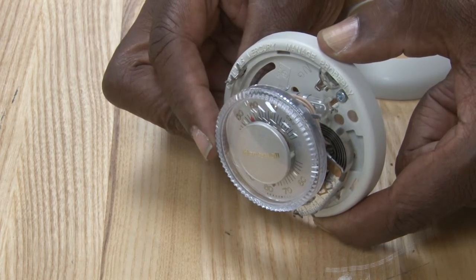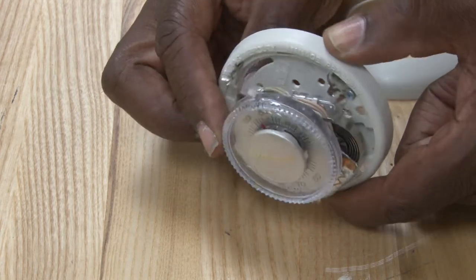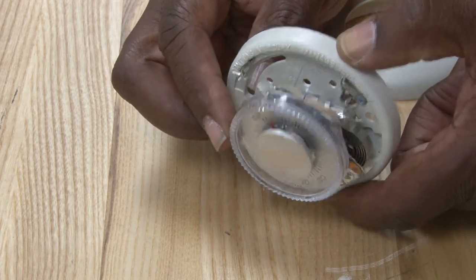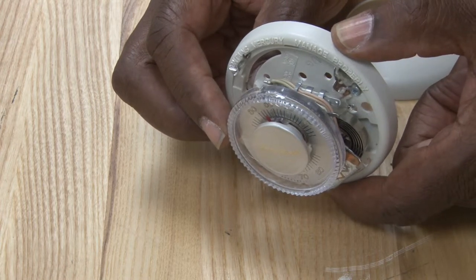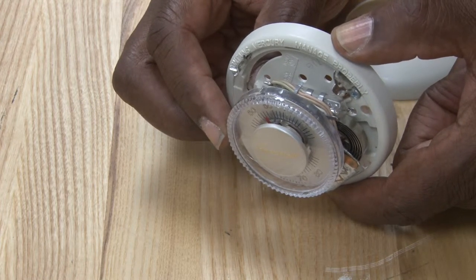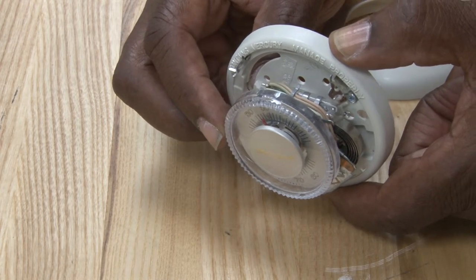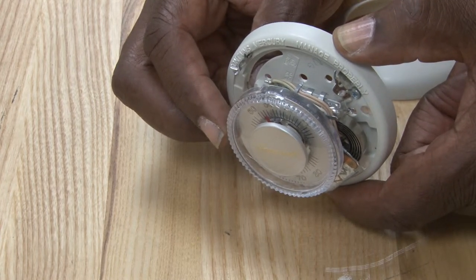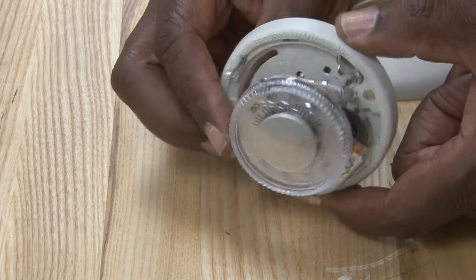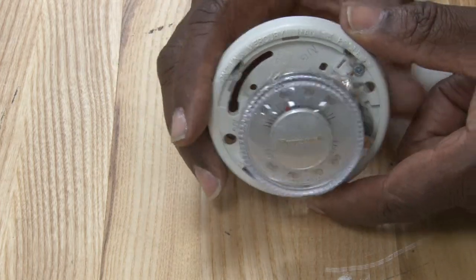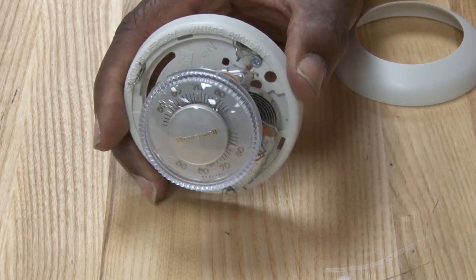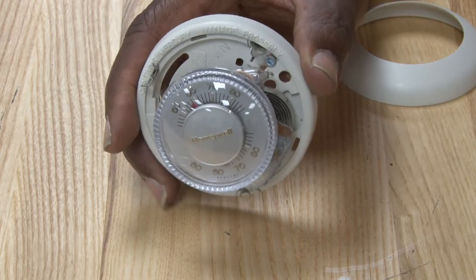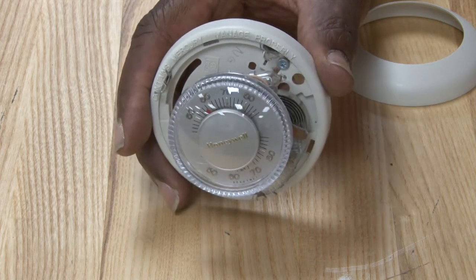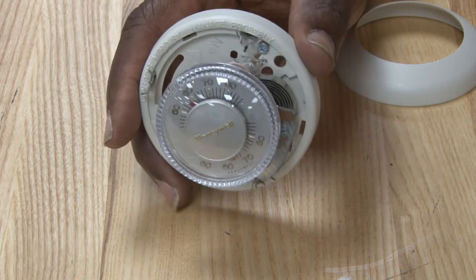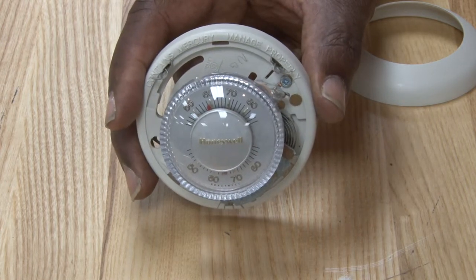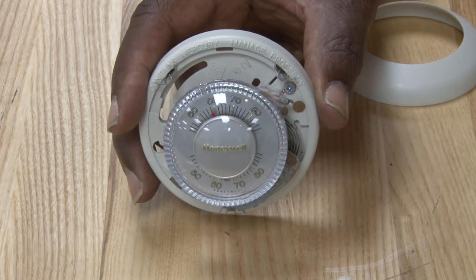This is one type. This old style, they're getting rid of these because, of course, mercury is a hazard. It's toxic. So because of that, digital thermostats are becoming more popular these days. Matter of fact, digital is a lot more accurate and reliable than this mercury bulb style, this old style. One of the problems was, you can see the mercury's moving back and forth. And if this wasn't leveled on the wall correctly, it could throw the thermostat out of calibration. So, very sensitive to levelness on the wall.